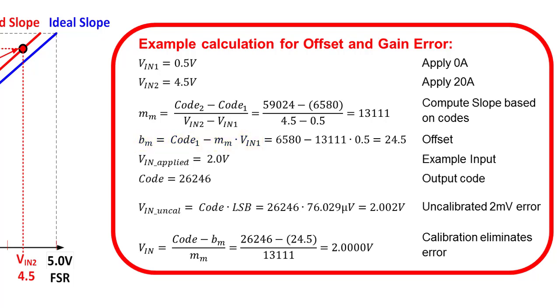Once you have the offset and slope, you can correct the error for any input. In this example, we apply a 2 volt input signal. The uncalibrated reading for this is 2.002 volts, so there is a 2 millivolt error from gain and offset. Applying the correction using the calibration coefficients, we can eliminate the error and determine the actual input signal of 2 volts.